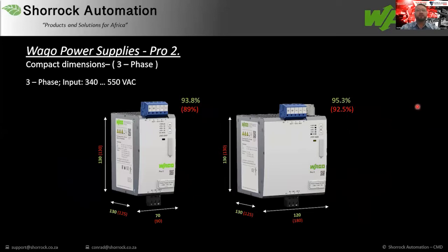Also, we offer a range of three-phase power supplies. And there are some nice features on these three-phase power supplies, such as the voltage input can be between 340 volts AC and 550 volts AC. That means you can use it on your 380 applications or your standard 380 supply voltage applications. But at the same time, it's also for the customers who use 525. The same power supply will work there. Now, in the industry, we often find that power supplies cannot handle higher 525 applications. So the customer has to install a small control voltage transformer in the bottom of the panel. And with this power supply and the size being so small, it actually saves a lot of panel space.